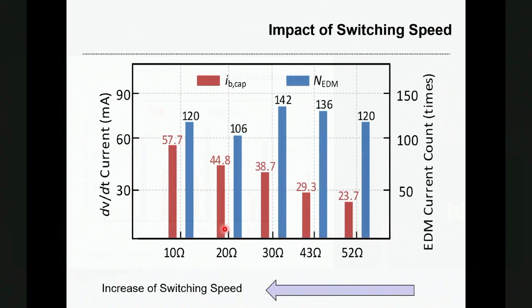And we have measured the dV/dt type of current, which is basically a capacitive type of current, and also counted the occurrence of the EDM current. As you can see, with the increase of the switching speed, there will be higher dV/dt current because it's a capacitive type of current. With high dV/dt, you will have more capacitive current. And the EDM current count does not change much with the change of the switching speed.